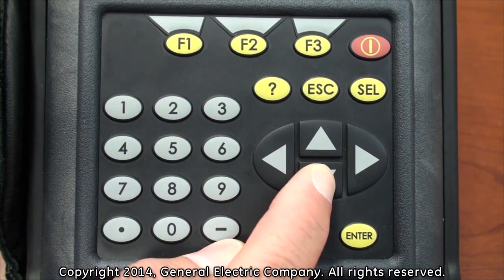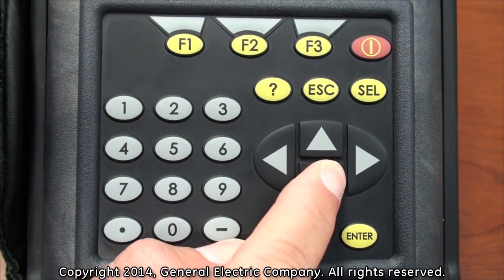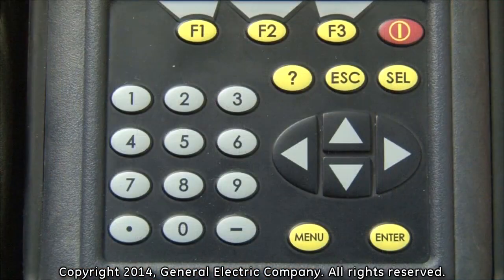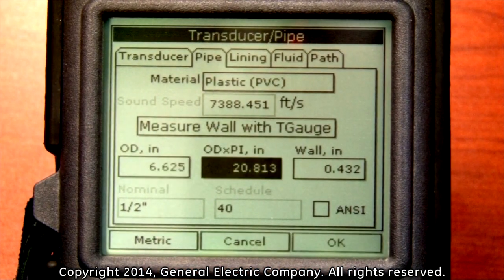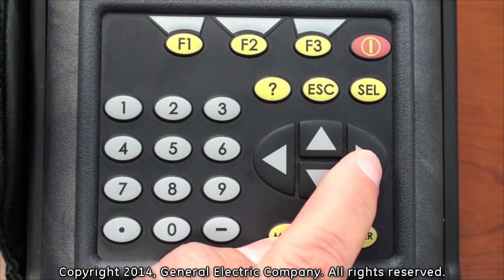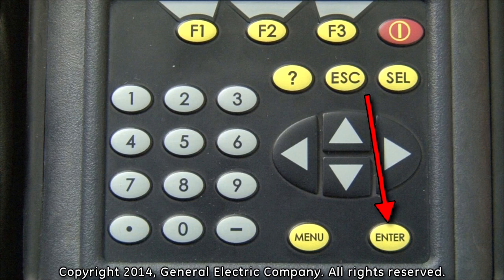The next option to program is the wall thickness, which will be covered in another video segment devoted entirely to measuring wall thickness. Once your wall thickness is measured, use the down arrow key to highlight the outer diameter input field. After measuring the outer diameter of the pipe, press the enter button and use the number keys on the keypad to input the outer diameter. Once the diameter is entered, press the enter button again. You do not have to input any value in the OD times PI field as it will automatically be calculated after putting in your outer diameter. Use the right arrow key to move over to the wall thickness input field and press enter. Input the value of the wall thickness measured from the wall thickness gauge by using the number keys on the keypad. Press the enter button once you have input the wall thickness value.